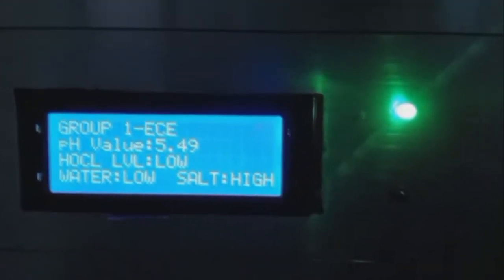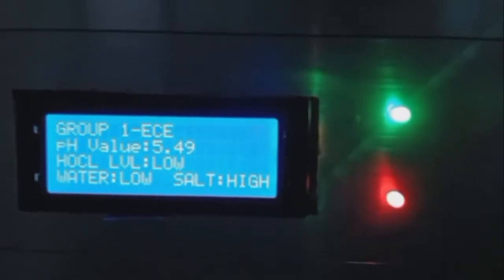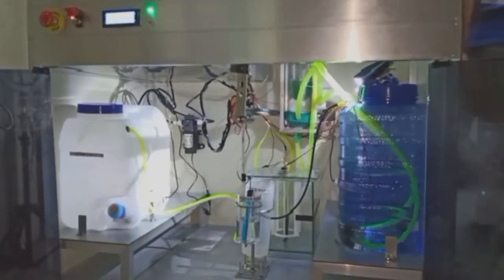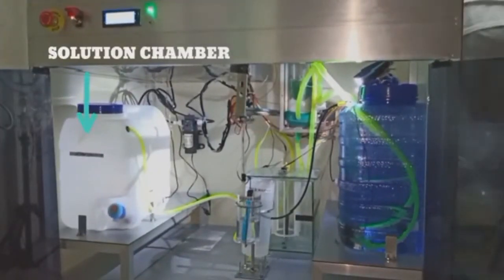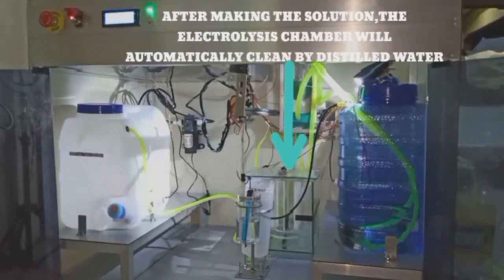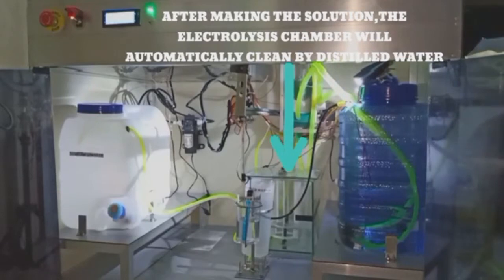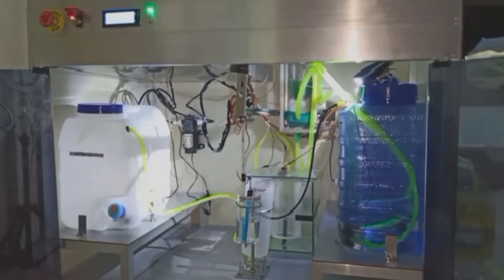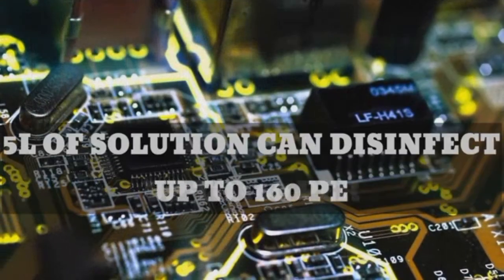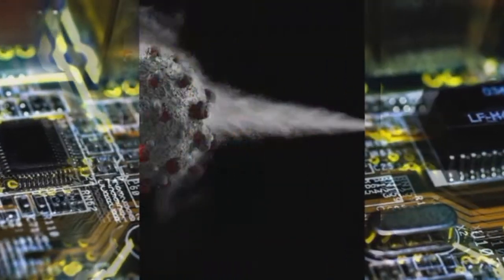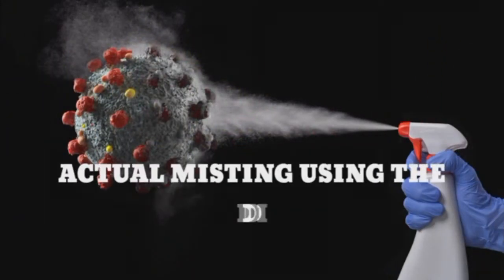After the electrolysis, we got a 5.49 pH level, which means we passed the set pH level. This is the solution chamber of our device. After making the solution, the electrolysis chamber will be automatically cleaned by distilled water. Five liters of solution can disinfect up to 160 persons. Actual misting using the disinfectant solution.